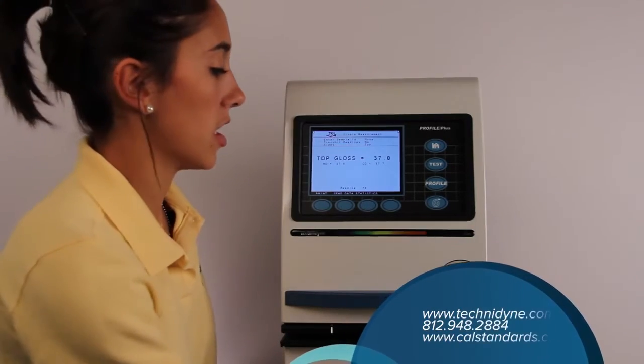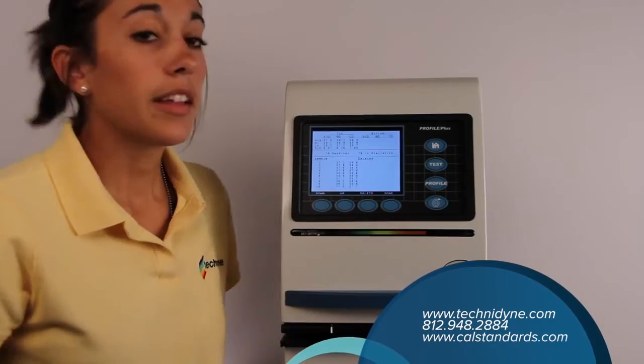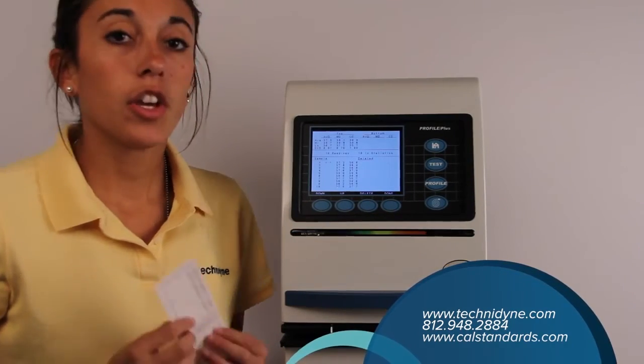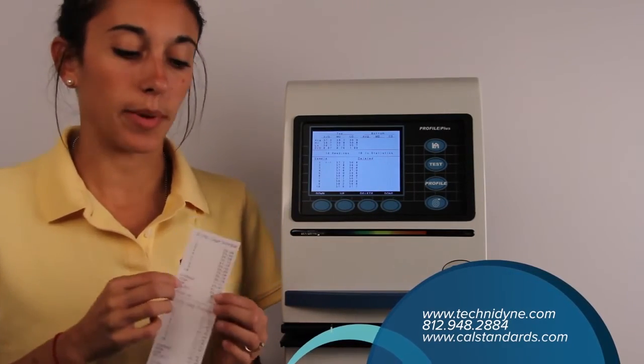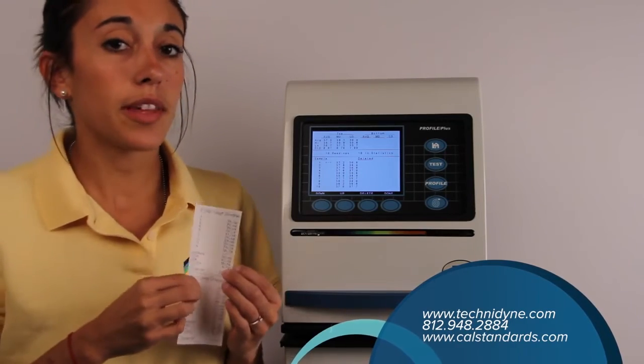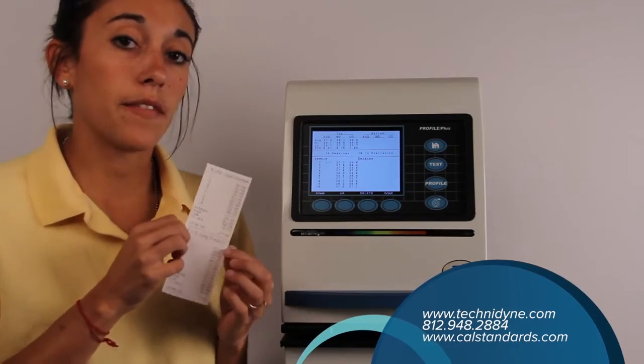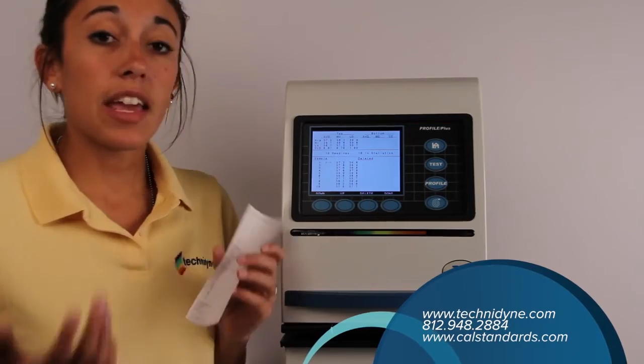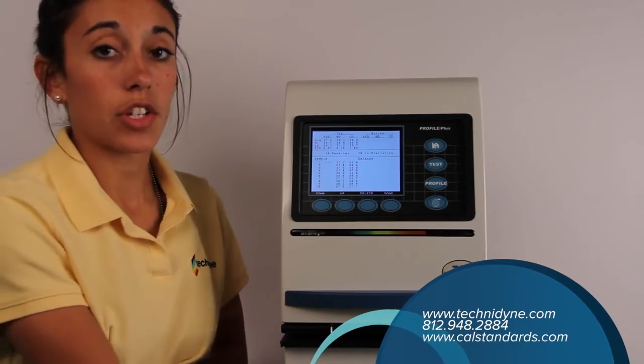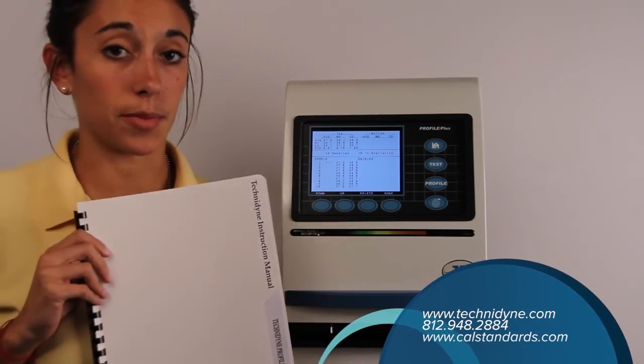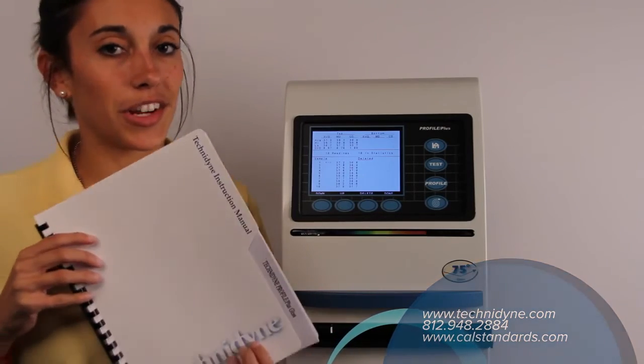Once we've gone through all 10, we want to press the Statistics Soft button. Now is when we'll need our printout. You want to verify that the average that your instrument gives you matches or is within plus or minus 1 of the average on your printout. If it's not, or if you have any other questions, you can refer to your Technidyne operator's manual, you can call Technidyne, or you can check out the website.